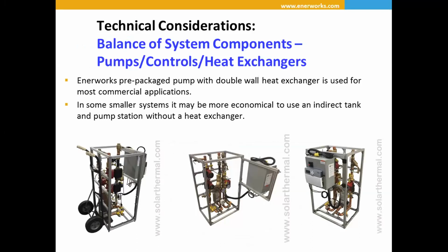The balance of the system, and this is something that we'll talk about a little bit later. So the pump station and controls. So this is our pump station controls. We used to make one that was very, very large, called it the piano. And in light of shrinking mechanical rooms and just the cost of having larger mechanical rooms, we came up with a pump station that is more compact. And this is pressure tested, pre-wired, and essentially can fit through a standard doorway.